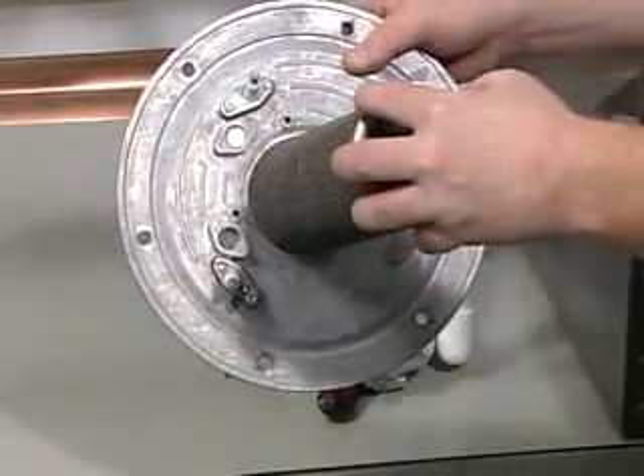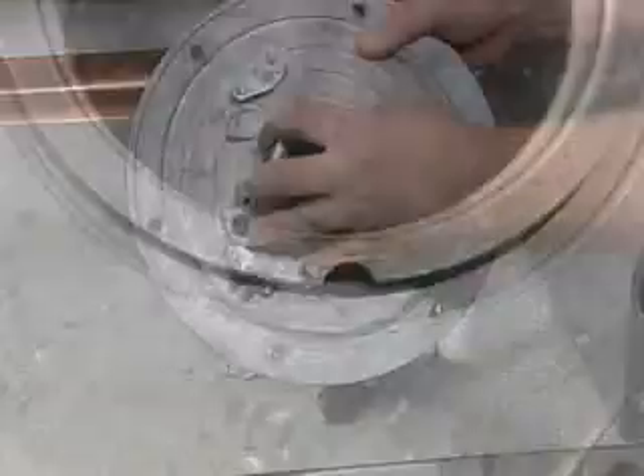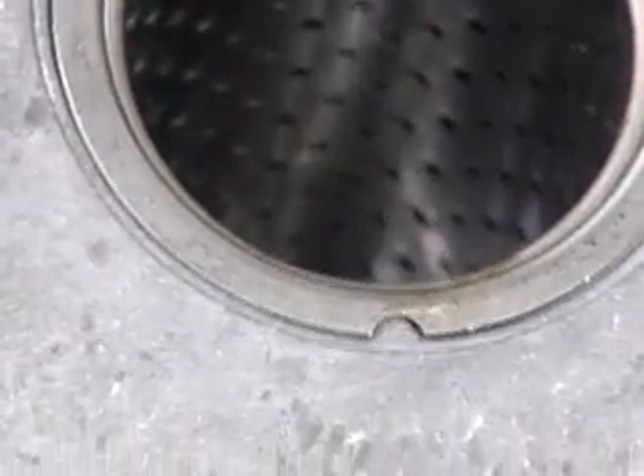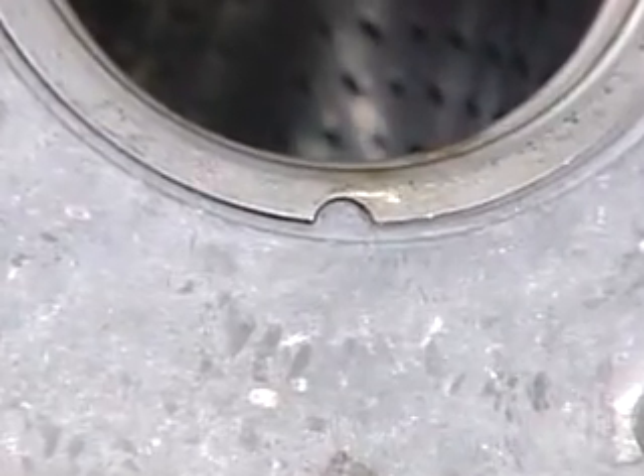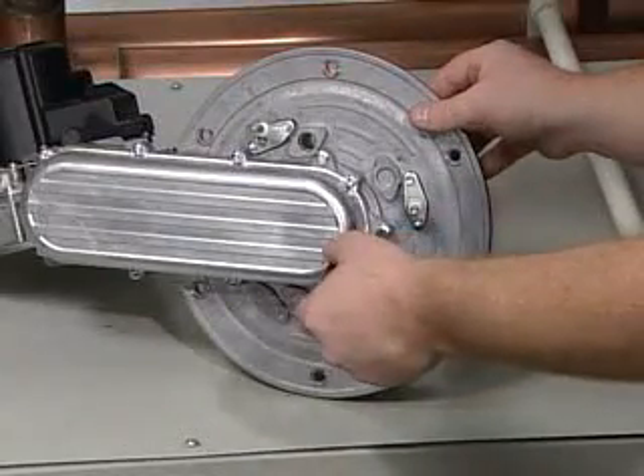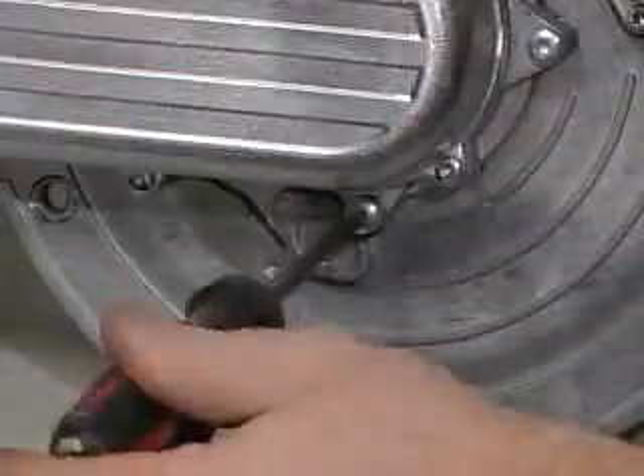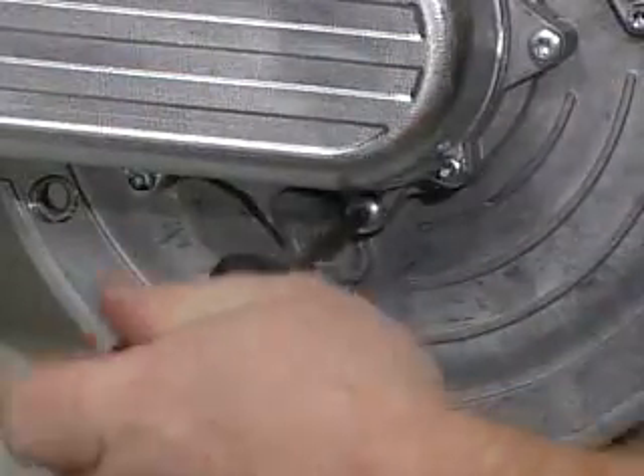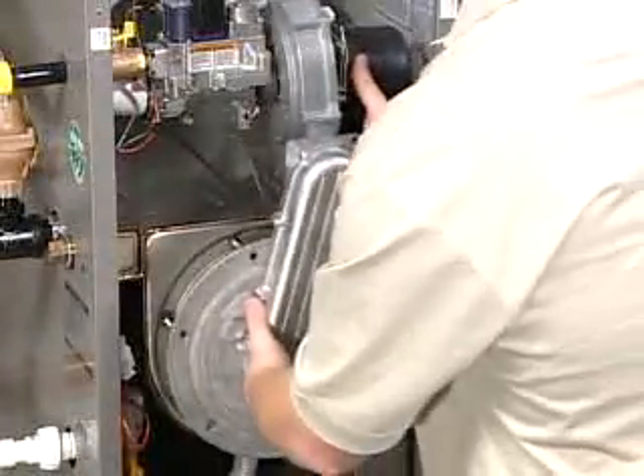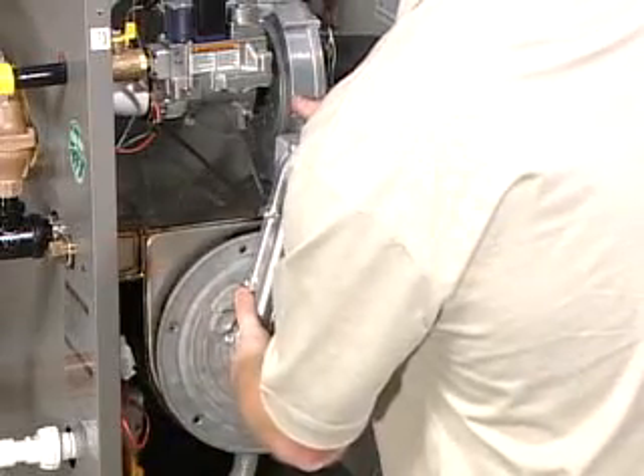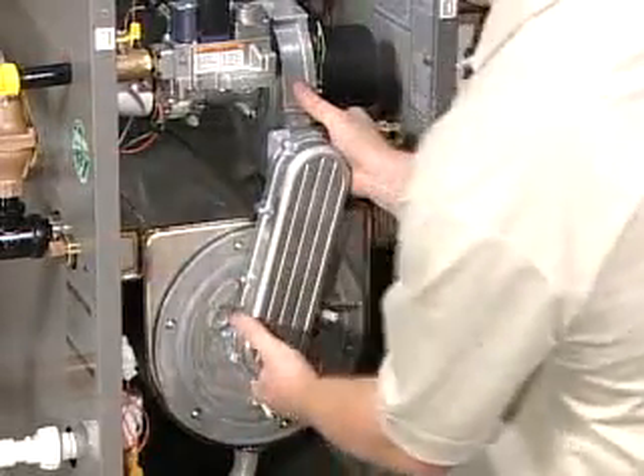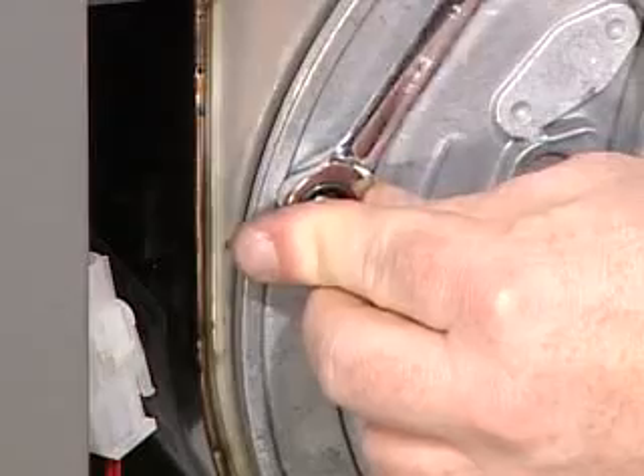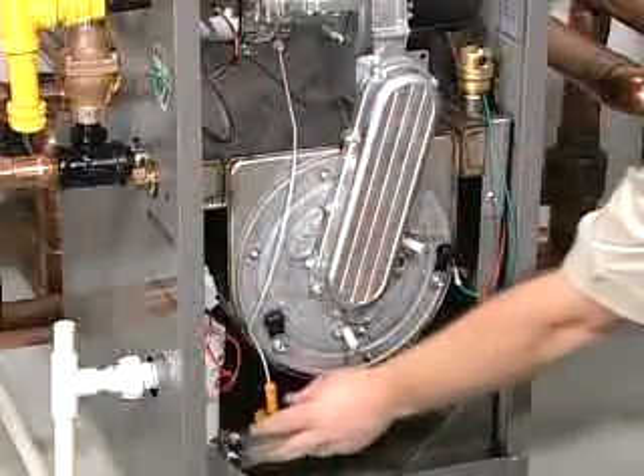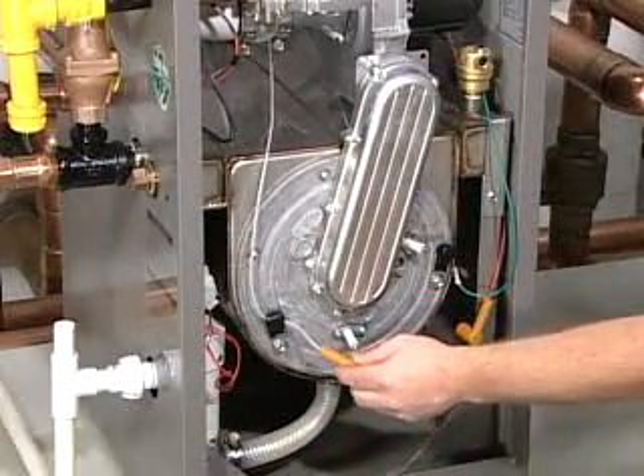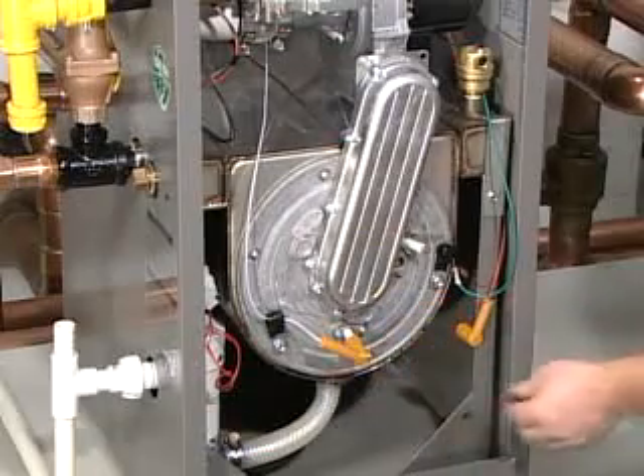Reinstall the burner back into the heat exchanger door. Ensure that the notch on the burner matches the corresponding notch on the heat exchanger door. Reattach the gas-air arm to the heat exchanger door with the 3 Torx screws. Carefully reinstall the heat exchanger door and secure it with the 6 10 mm nuts. Reconnect the wiring from the flame rod, spark igniter, and ground terminal to the front of the heat exchanger door.